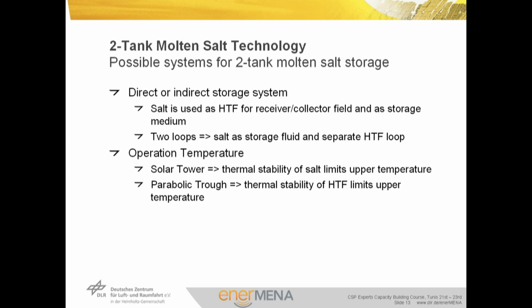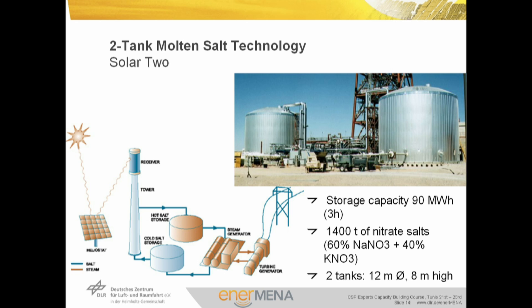The first large-scale implementation of a two-tank molten salt storage system was the SOLAR2 research project. During the 1990s, hot molten salt from a central receiver was stored directly at 565°C. This storage system shows a thermal capacity of 90 MWh, allowing storage-based operation for 3 hours. The temperature difference between hot and cold tank was 275°C. The main components were two tanks with a diameter of 12 meters and a height of 8 meters, containing 1,400 tons of a eutectic mixture of sodium nitrate and potassium nitrate.